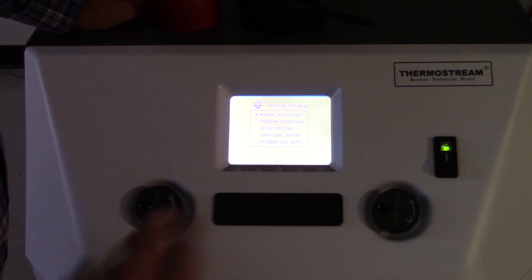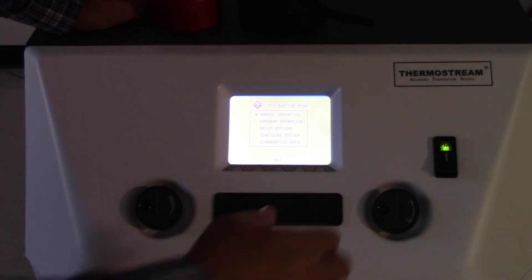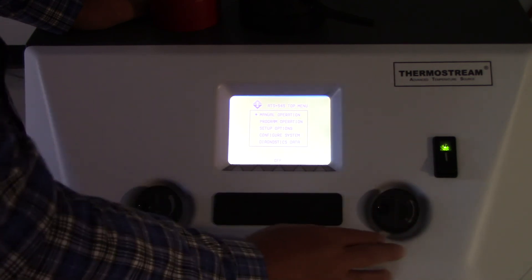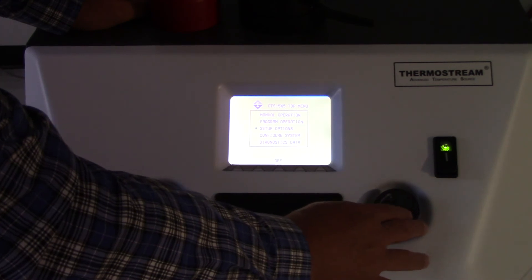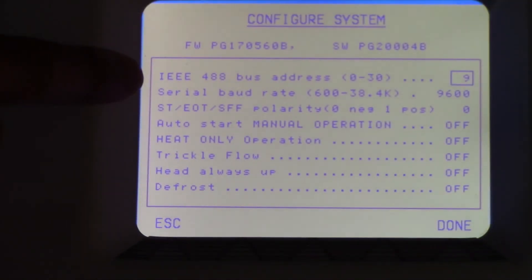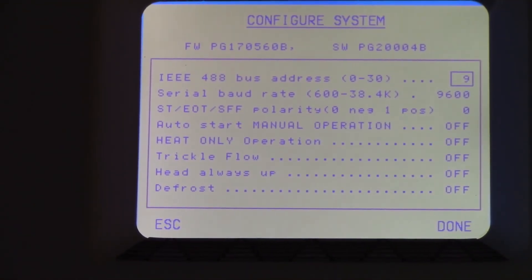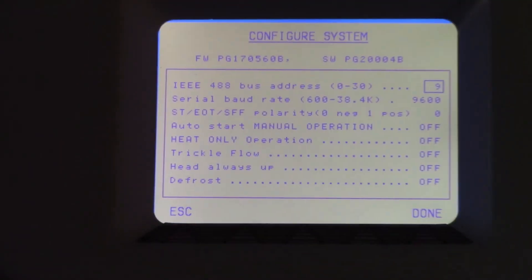If I want to configure the system — maybe for some parameters for DUT control, or to adjust the IEEE address — I go down to configure system, select it, and now you'll see that I've got the IEEE 488 address, bus, baud rate, etc. There are lots of different parameters that the user can define at the time of use.